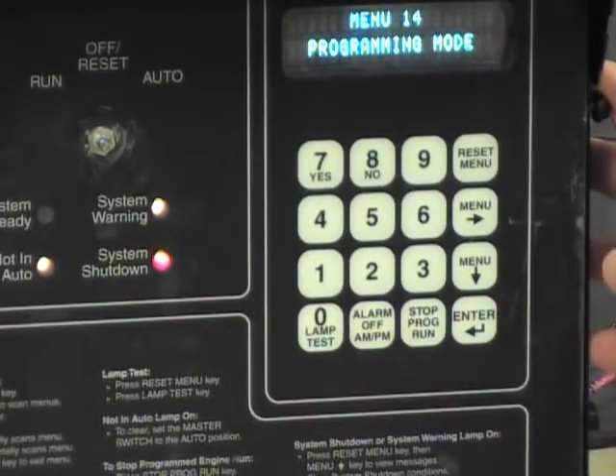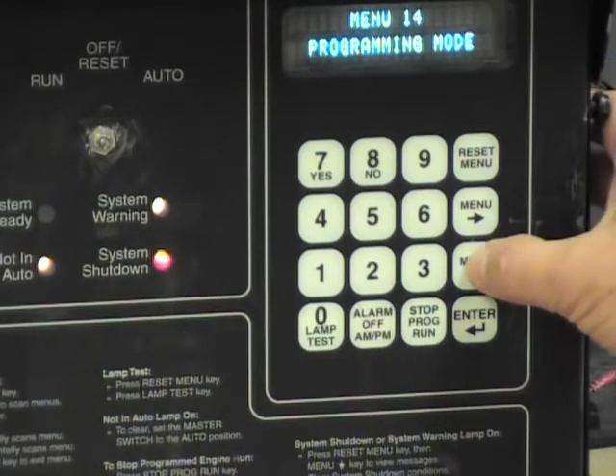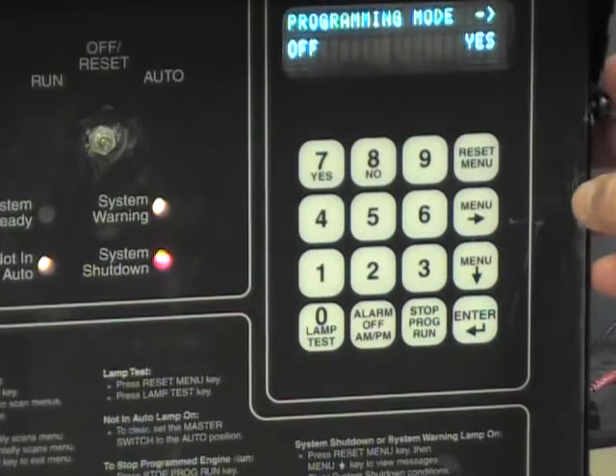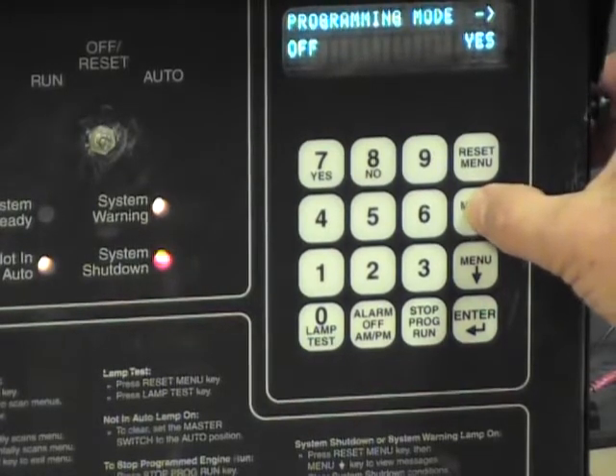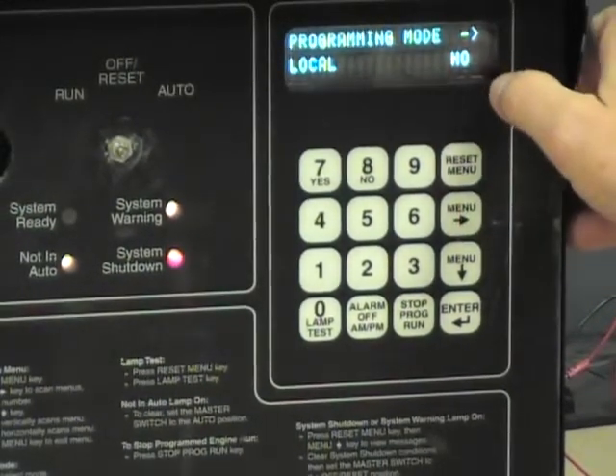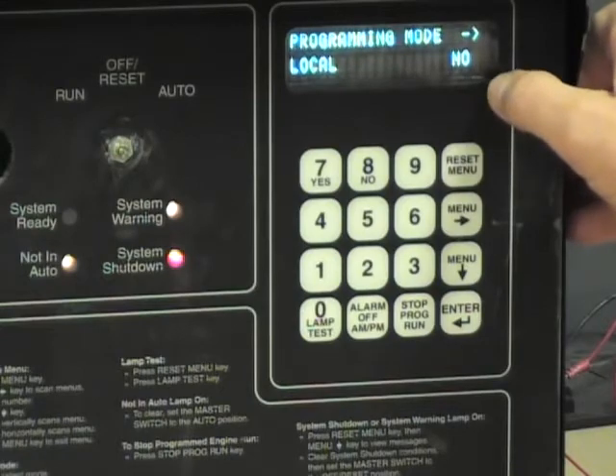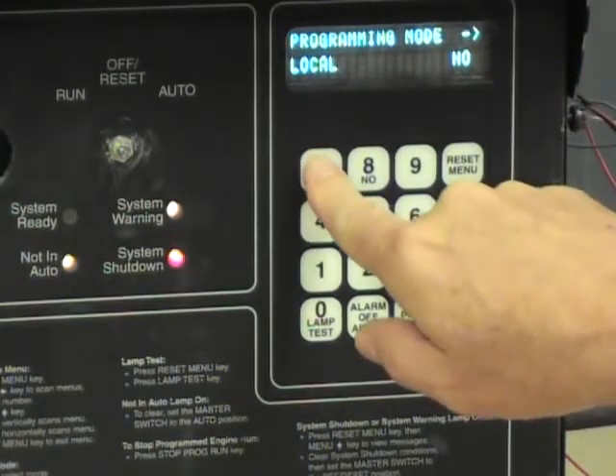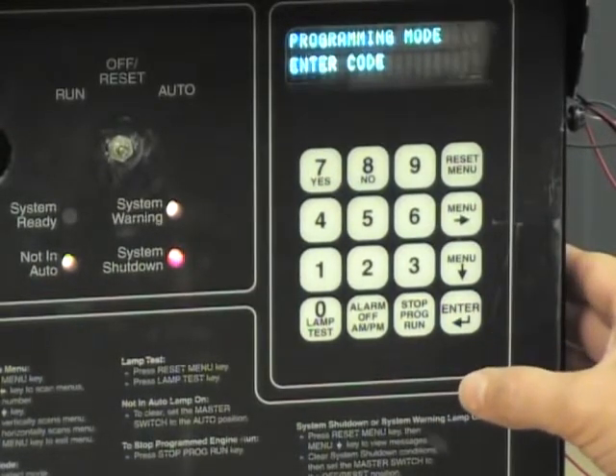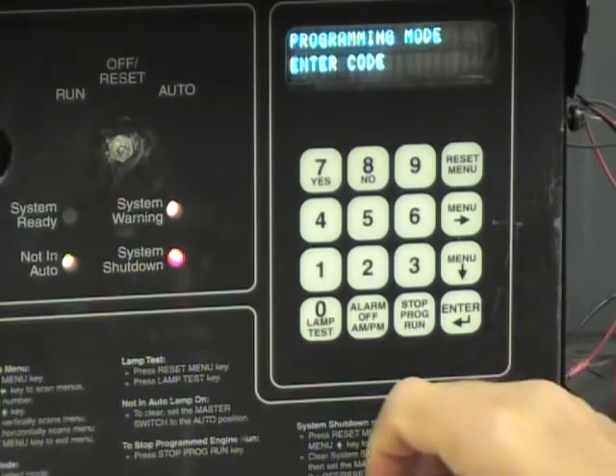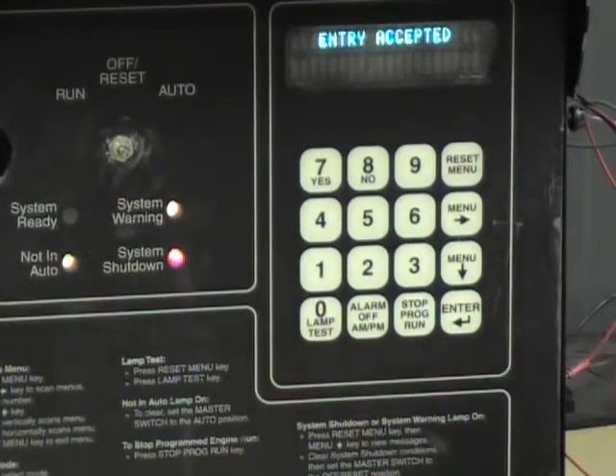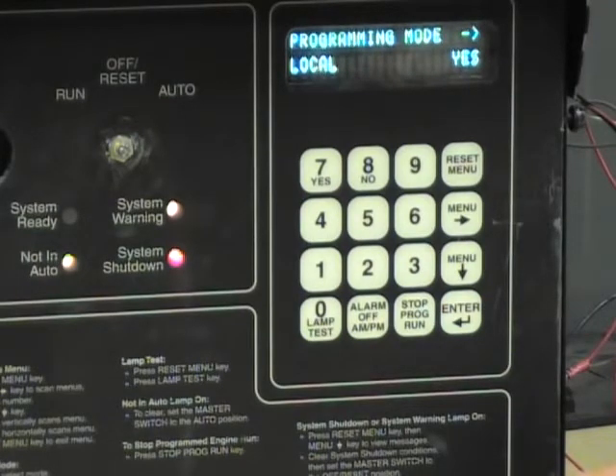That puts us at the point of programming mode. Now I'm going to push the down arrow key, which indicates we're in programming mode. The next thing we want to do is hit the left arrow key and go to local. Notice that right now we're in the no condition for programming mode — I'm going to press yes, then hit enter. It's going to ask us for a password. The default password from Kohler is a simple zero. I'll press zero and enter, and it says entry accepted — now we are in programming mode.